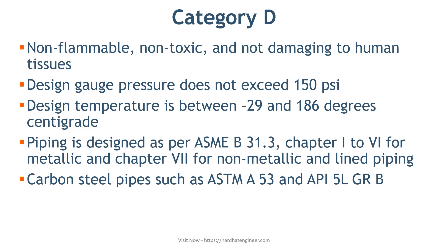The third condition is design temperature. The design temperature is between minus 29 to 186 degrees centigrade for this service, so this service handles moderate temperatures. Most utility lines such as water, air, etc. fall under this type of fluid service. Piping is designed as per ASME B31.3 chapter 1 to chapter 6 for metallic, and chapter 7 for non-metallic and lined piping. Normally, carbon steel pipes such as ASTM A53 and API 5L Grade B are used, and it may be galvanized or painted.